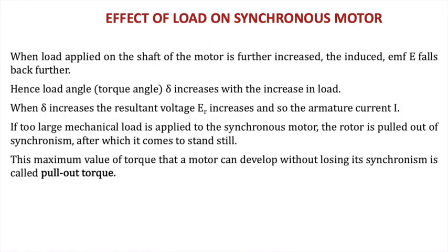So when there is an increase in the load, this delta increases. As you go on increasing the load, the load angle will go on increasing, but there is a limit to the increase in the load angle, and that is normally 90 degrees. If too large a mechanical load is applied to the synchronous motor, the rotor will be pulled out of synchronism, and it will come to a standstill.